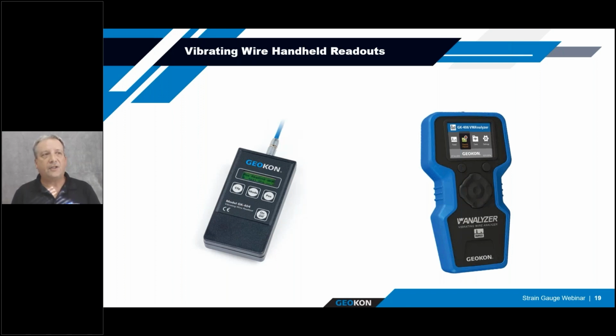On the right is the GK406, a more advanced handheld readout. It's a great tool for diagnostics: it can store data, convert raw readings into engineering units if necessary, and create a PDF report showing diagnostics of the instrument such as decay ratio and other information that may or may not be useful. If you're troubleshooting an instrument, it's not a bad tool to have, but if you're just trying to get readings, the GK404 on the left is the way to go.